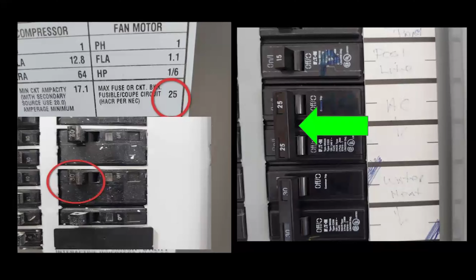So that's why it's important to check that out. Sometimes even your electric water heaters will have max fuses on there. I haven't seen too many, but they do sometimes oversize the breaker. That's what they call it. So that's really important - you can see that's 25 amps, the 30 down below is the red flag, but we want to see the 25 amps. I was in a discussion group once with an inspector who was newer, and he said, 'they don't make 25 amp breakers.' I said, 'yeah, they do, I've seen them, I've put them in.' There they are - had to get a picture of it and put it on there.